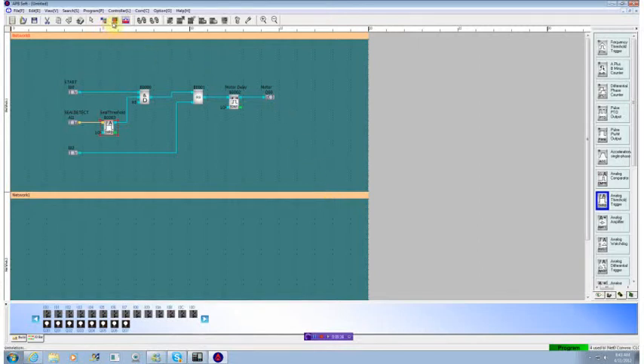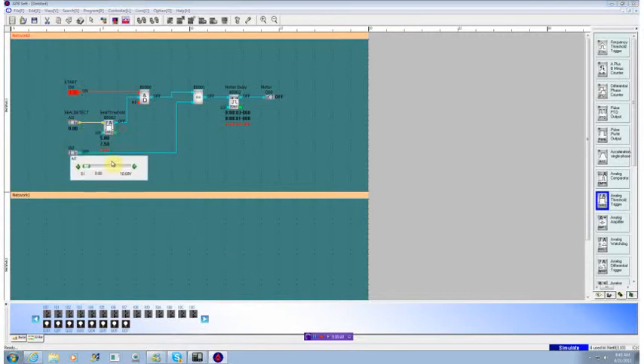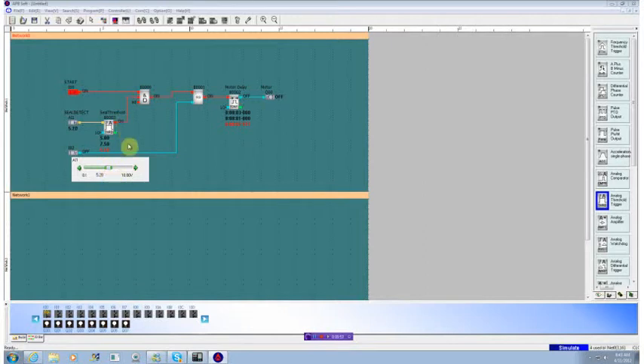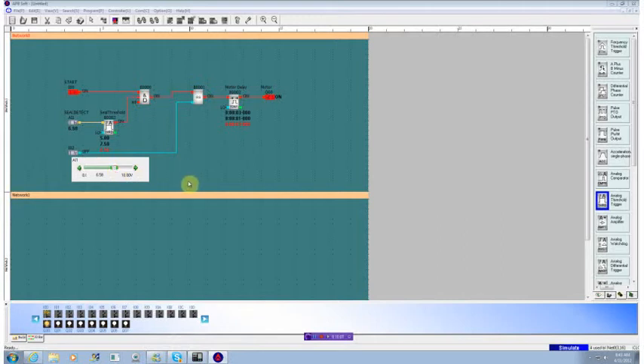Run the simulator. Hit the start button. This time when we select our analog input, we see that we have a slider. And so we've got an on threshold of five and off threshold of seven point five. As we slide our slider up and we hit five, we see that the input turns on. If we continue to slide it up, when it hits seven point five, it turns it off. So that isn't exactly what we wanted in this situation. It gives us a band of valid values that would turn it on and off.